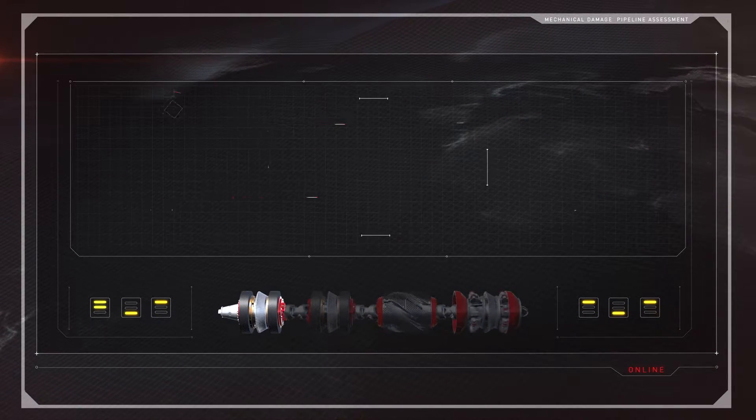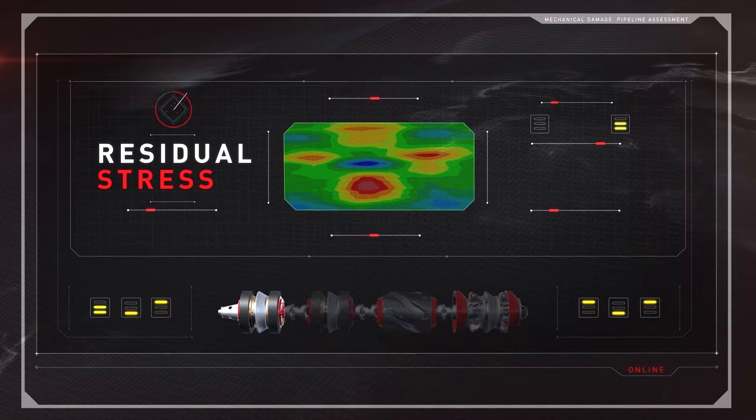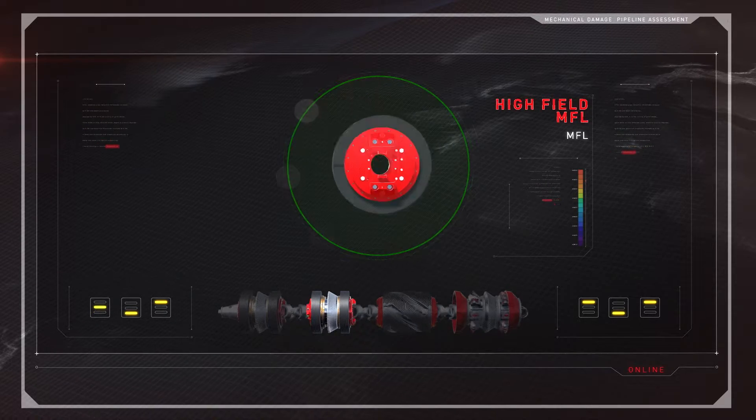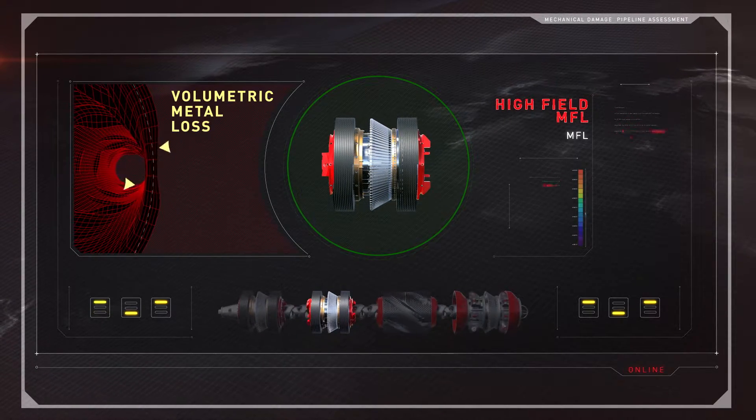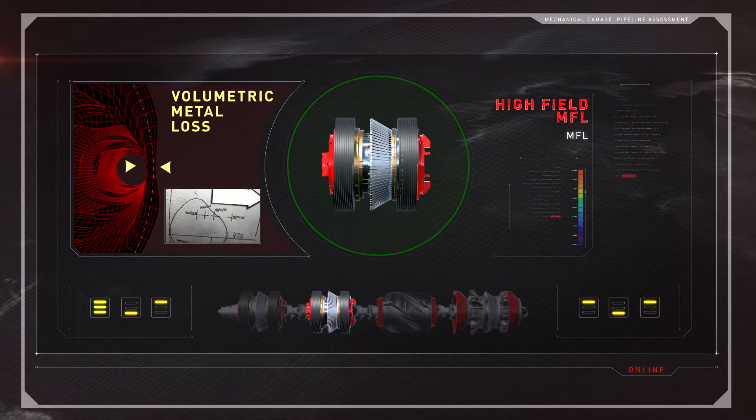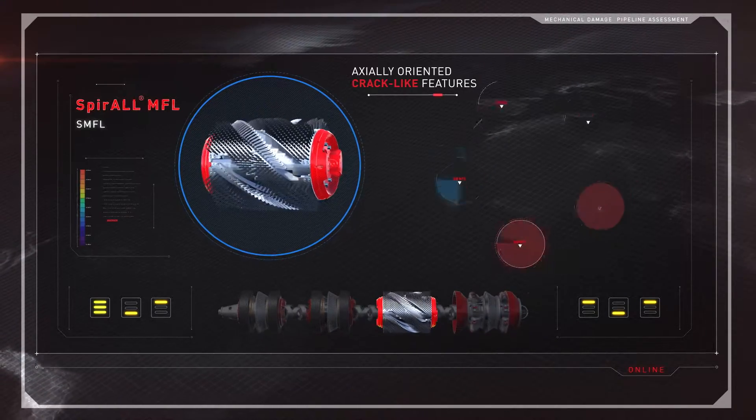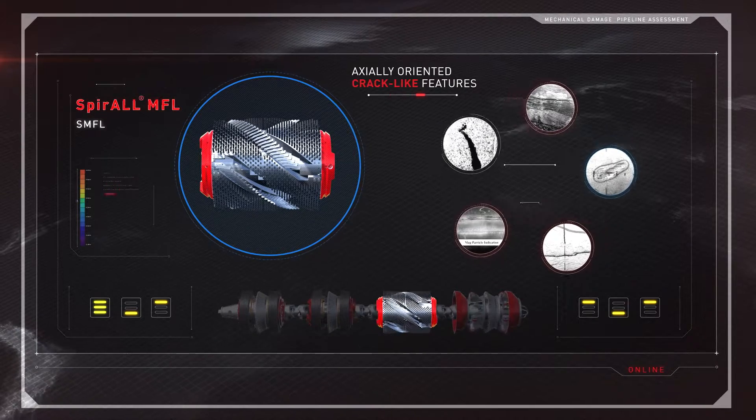For example, as well as residual stresses associated with dent re-rounding. High resolution magnetic flux leakage locates volumetric metal loss, including within a dent region. SpirALL MFL detects axially oriented crack-like features such as hook cracks and lack of fusion.